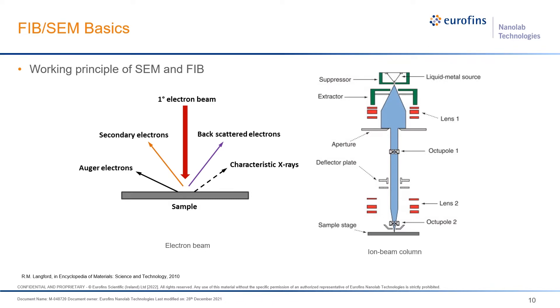When a beam of electrons is emitted to the sample, it generates secondary electrons, backscatter electrons, Auger electrons, and characteristic X-rays. Typically an SEM image is generated by detecting secondary electrons, which can provide spatial resolution to sub-10 nanometers. A focused ion beam instrument is almost identical to an SEM, but uses a beam of ions rather than electrons. The focused ion beam can directly modify or mill the specimen surface via a sputtering process controlled within nanometer precision. In addition, ion beam-assisted chemical vapor deposition can be used to deposit material with a similar level of precision.